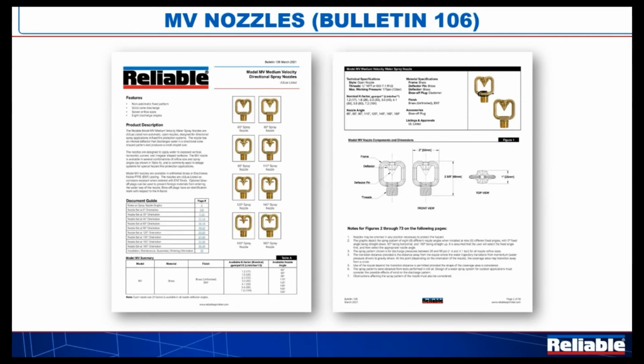That's because we've given you flow charts for each nozzle in different orientations. We've got 8 nozzles, 8 discharge angles, 8 cone shapes, let's call it, coming off the deflector. And we've told you how to position those 9 different ways, from 0 degrees pointing straight down to 180 degrees pointing straight up. 9 positions around the one half of the clock gives us 72 flow charts. Again, document number 106 is going to have some additional information on it: dimensional, K-factors, finish, and things like that.